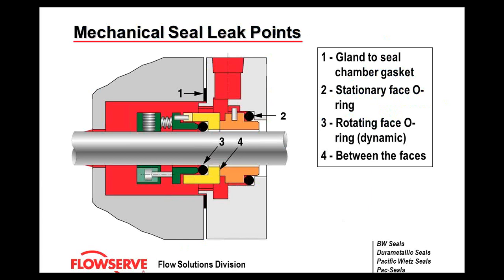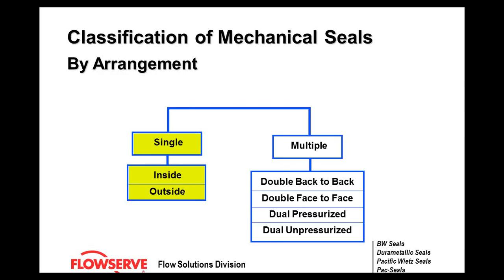Item number three is the dynamic o-ring. That o-ring is called dynamic because it actually moves with the mechanical seal — it tracks with the springs. As it tracks, there's a possibility it can erode, wear, or fret, leading to a leak. With dirts, contaminants, or off-design operation, these can all wear the seal and cause a leak.